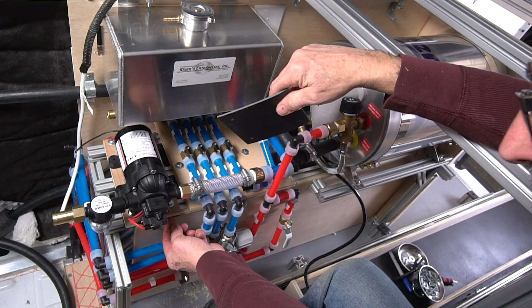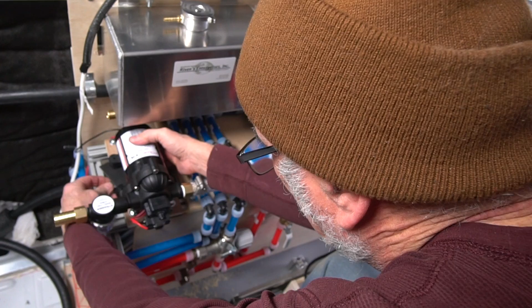The reason I set this little bit of soft tubing in between the pump and the system is all of our Propex is rigid. This softness is going to mitigate the vibration caused by this pump. This pump is sitting on a platform that's sitting on a rubber gasket. There will be another rubber gasket installed under the pump. And if you notice, I isolated the pump on its own tray in order to minimize that vibration as well.